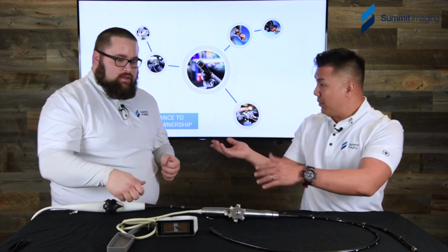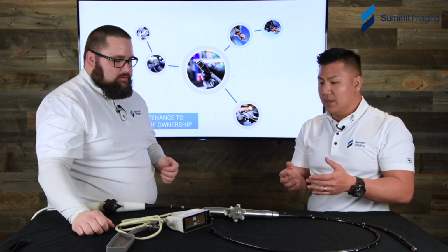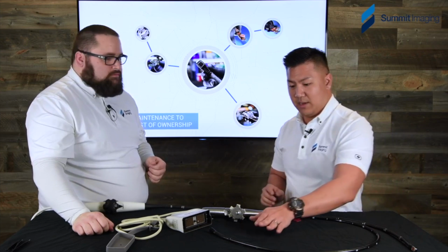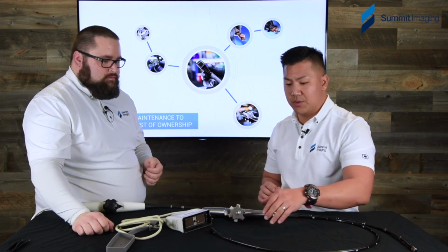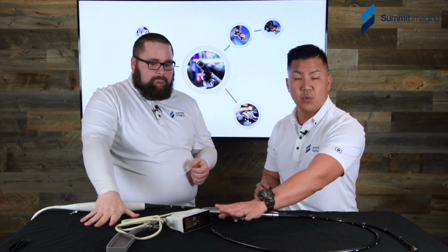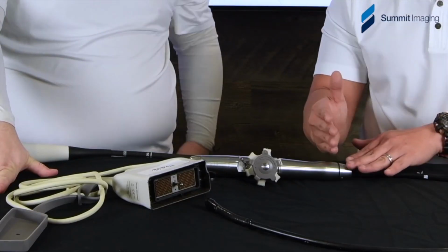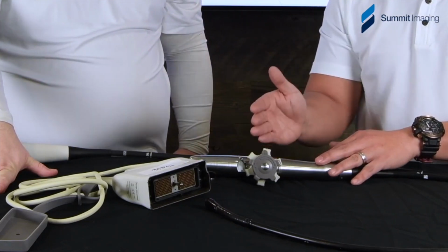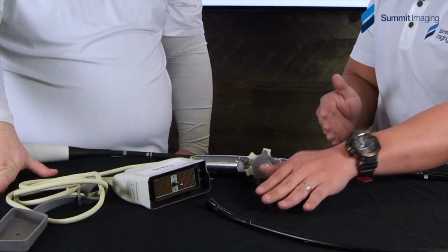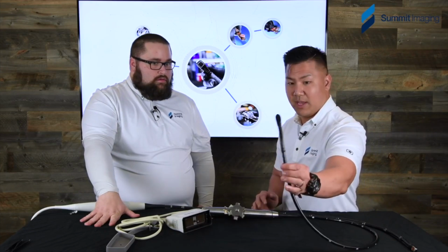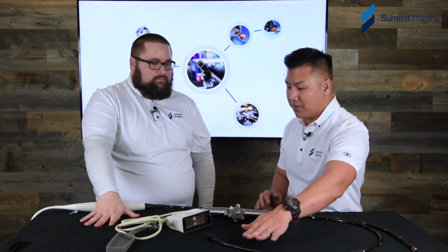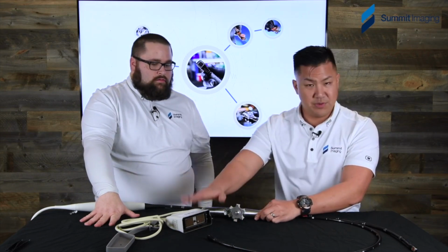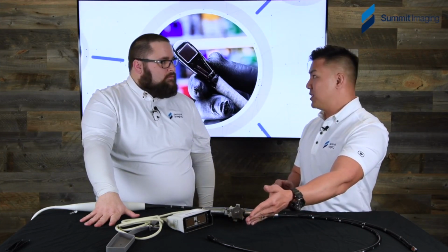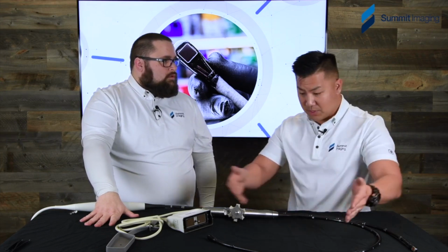So I think one thing that Kyle is talking about is really caring for and protecting the sensitive part of the transducer, which in this case is the distal tip and the array up here, and keeping it away from impacting the really rigid and heavy duty, relatively speaking, parts. Because a light piece like this with the materials it's made of, taking an impact to what at this point is solid metal, is going to lose every single time, and that's the most valuable part of this transducer.